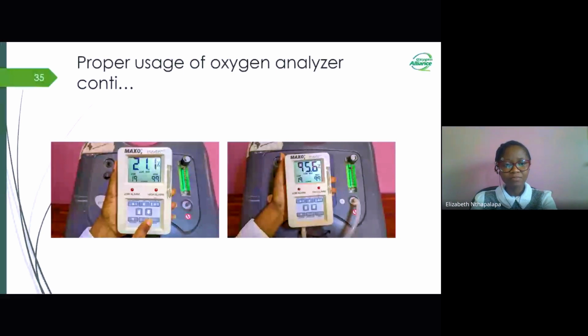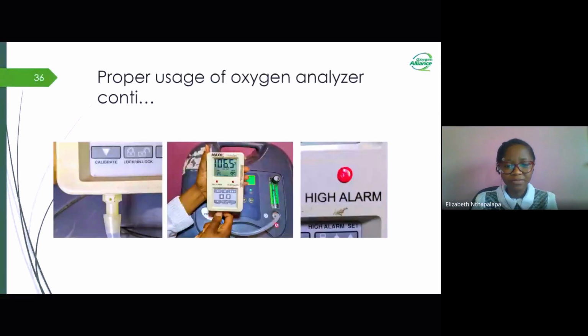The next slide, please. The steps that I showed you earlier were the proper things that we need to do as we're using the oxygen analyzers. But let us look at some of the things that we may happen to do that may distort the accurate reading of oxygen purity by our oxygen analyzers. This is an electrochemical analyzer, and from the very first picture, we have this hole which acts as the outlet of oxygen through the analyzer.